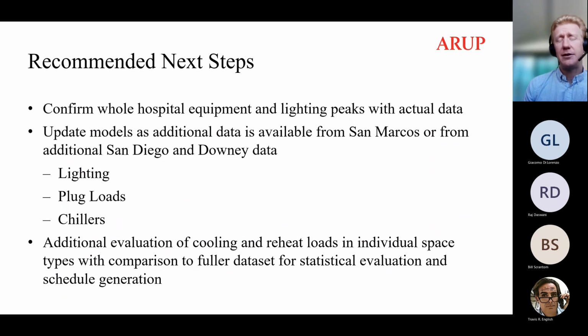And if so, then reflecting that back into the evaluation of sensible cooling load would be appropriate to determine why there's a disconnect between what's driving into the model and what is being seen on the energy use on the back end. And then finally, where there's a dearth of data at the moment for a statistically significant number of sample rooms or sample space types, additional evaluation of cooling and even extending that to reheat loads in those spaces would be beneficial, both to generate those schedules a bit more accurately using the fullest data sets and actual data points as opposed to extracting from graphs or percentile summaries. That would be a more accurate way, similarly to what was done with operating rooms and patient rooms, to really get a foundational starting point for what the schedules may likely be that are affecting behavior.